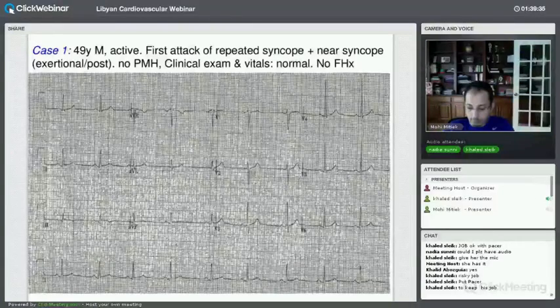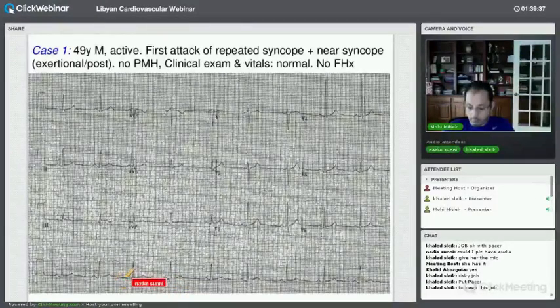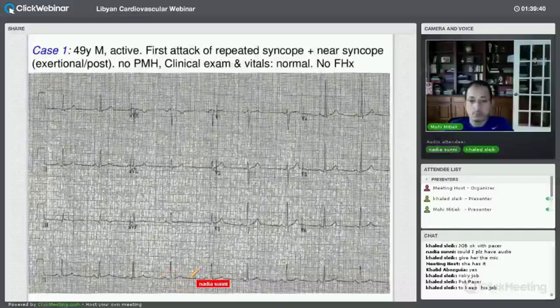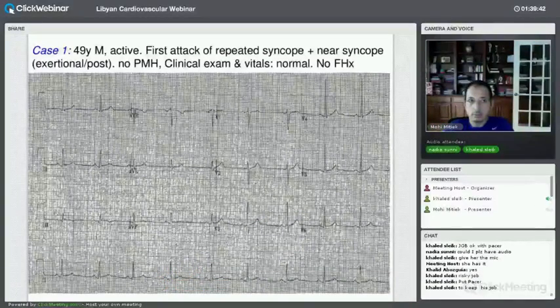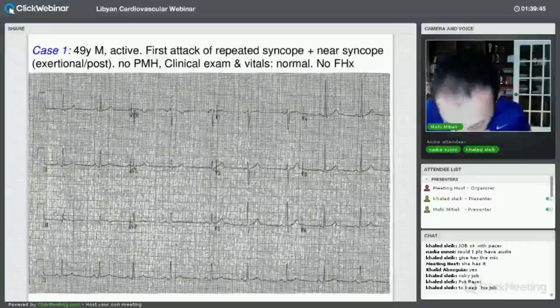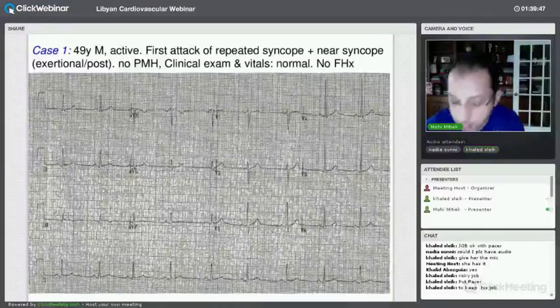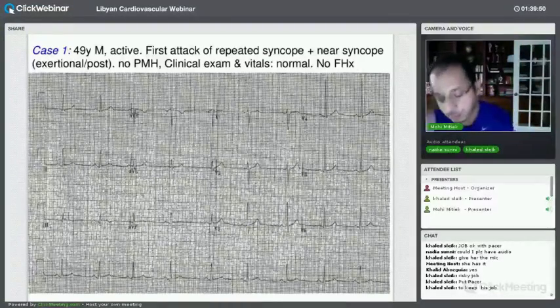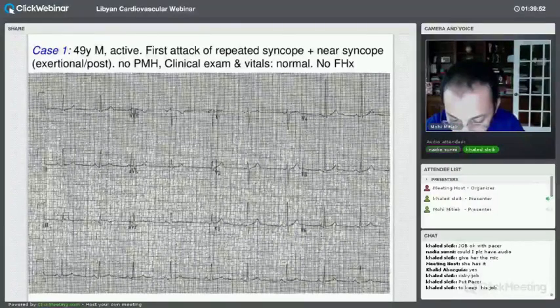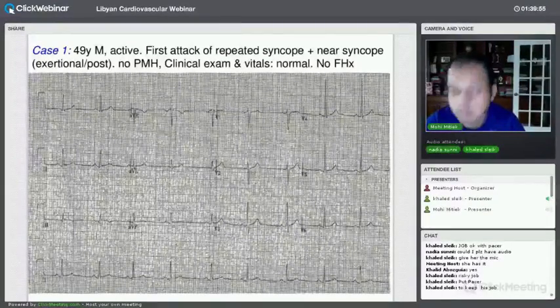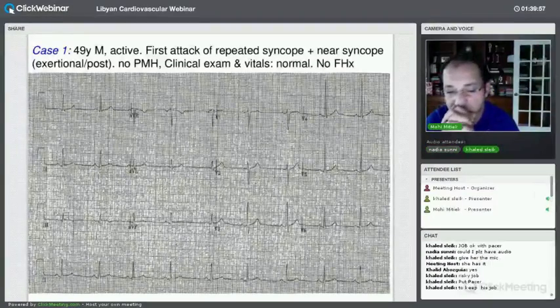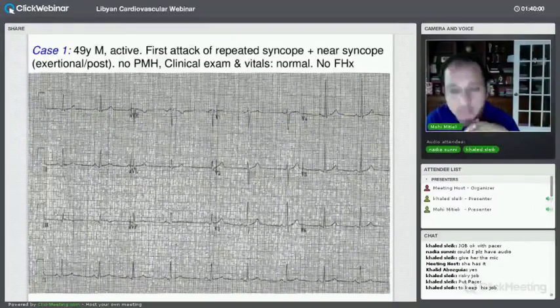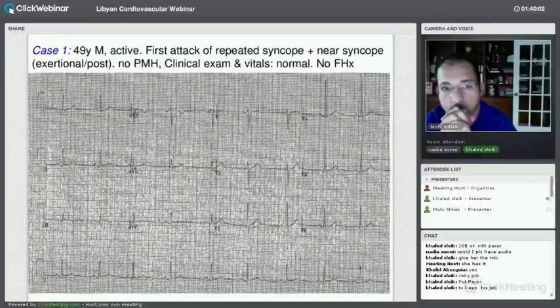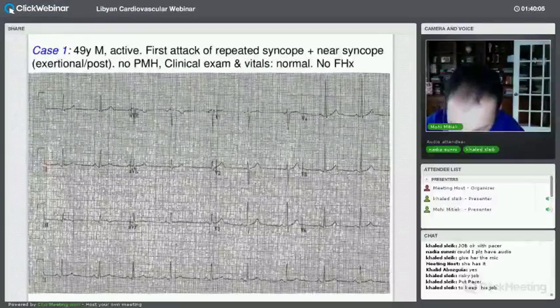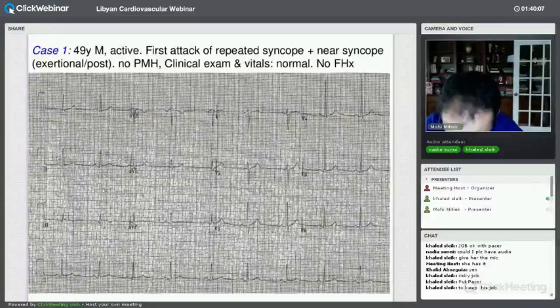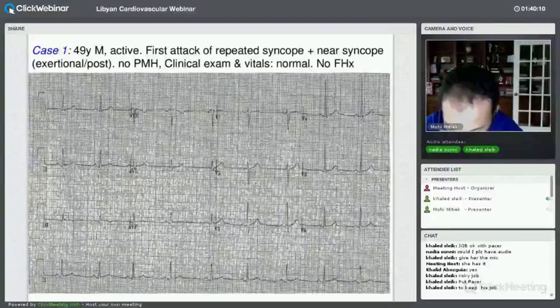With a rate drop response, meaning that if he suddenly started dropping his sinus rate, the pacemaker will start to pace him in AAI mode until it sees blocked ventricular beats, and then it will switch to a DDD mode. It will do that by looking at 2 and then 4 consecutive PP intervals.